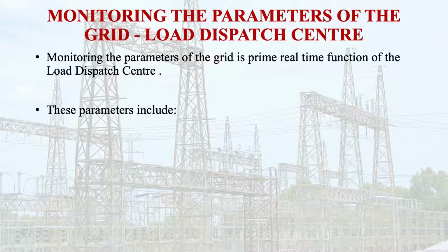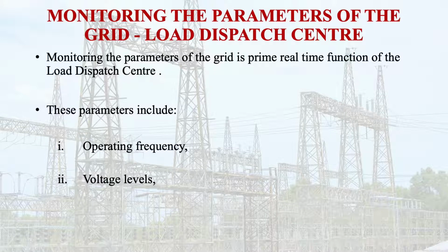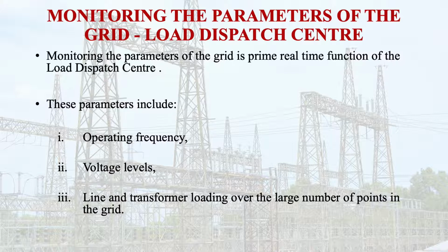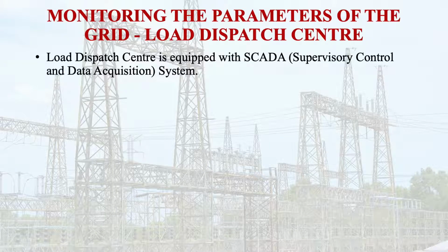These parameters include operating frequency, voltage levels at all points of the grid, status of the lines, and transformer loading throughout the grid, especially at crucial points. In order to help the grid operator monitor these parameters over the large number of points in the grid, the load dispatch center is equipped with SCADA. This is the supervisory control and data acquisition system.